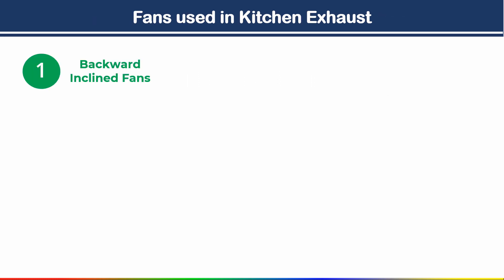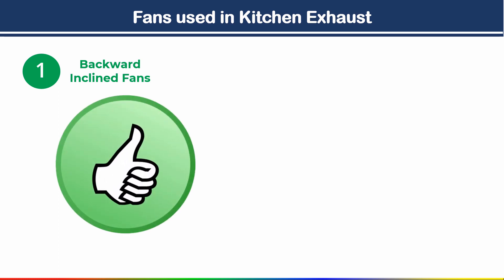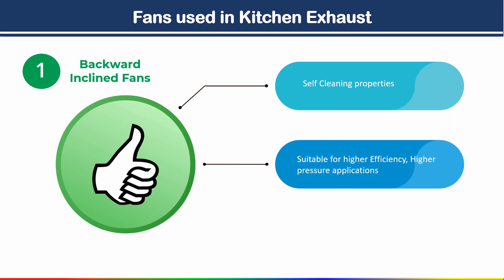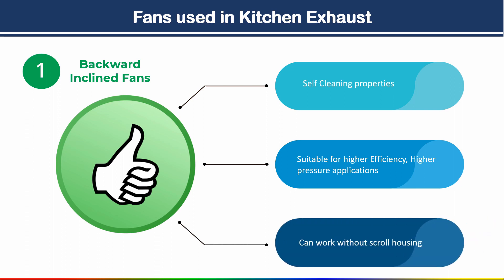Now let's see the fans used in kitchen exhaust systems. We generally use backward-inclined fans. The advantages of backward-inclined fans are: first, they have self-cleaning properties; second, they are suitable for higher efficiency and higher pressure applications; and third, they can work without scroll housing.